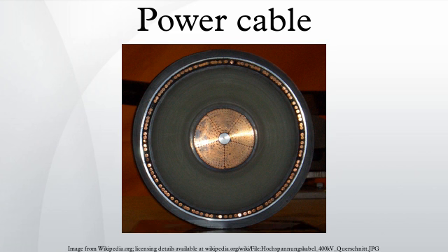The individual conductor shields of a cable are connected to earth ground at the ends of the cable, and at locations along the length if voltage rise during faults would be dangerous. Cables for power distribution of 10 kV or higher may be insulated with oil and paper, and are run in a rigid steel pipe, semi-rigid aluminum or lead sheath. For higher voltages the oil may be kept under pressure to prevent formation of voids that would allow partial discharges within the cable insulation. Modern high-voltage cables use polyethylene or other polymers, including XLPE, for insulation. They require special techniques for jointing and terminating, see high-voltage cable.